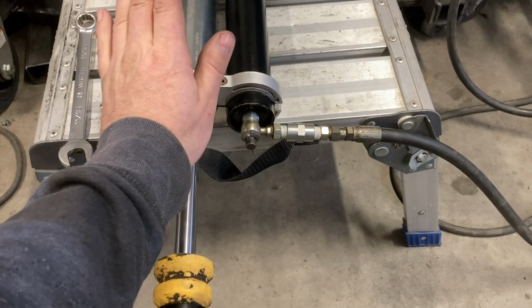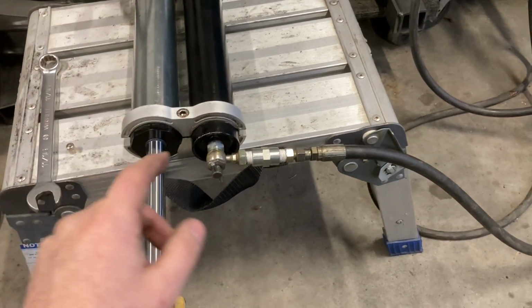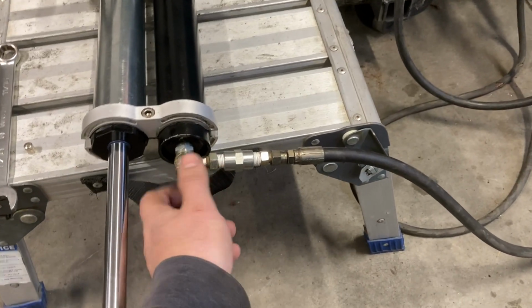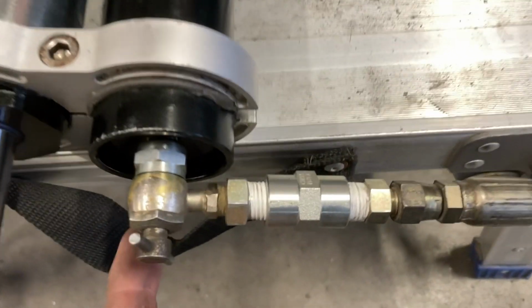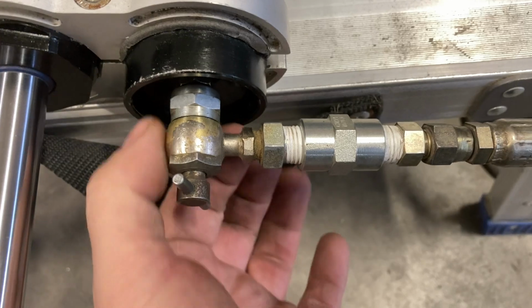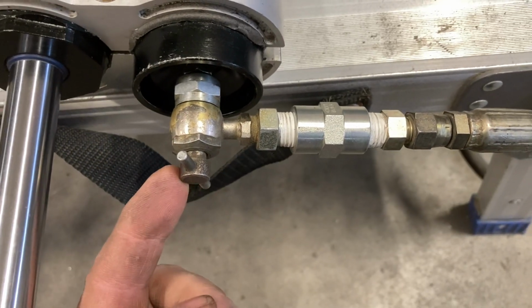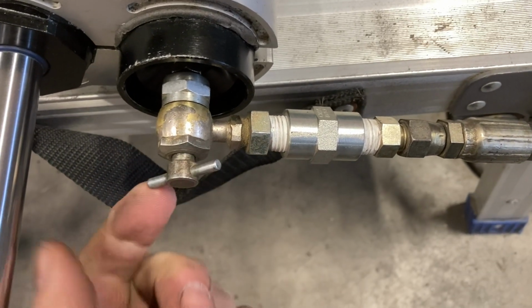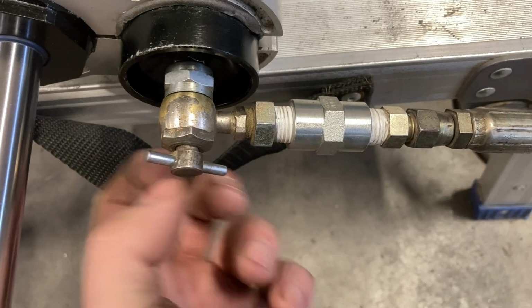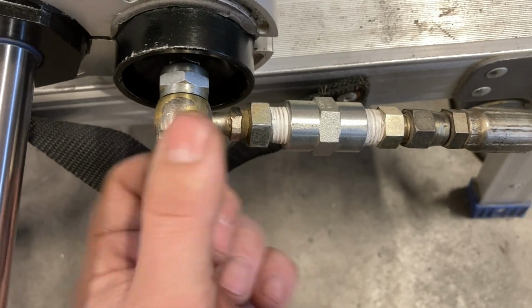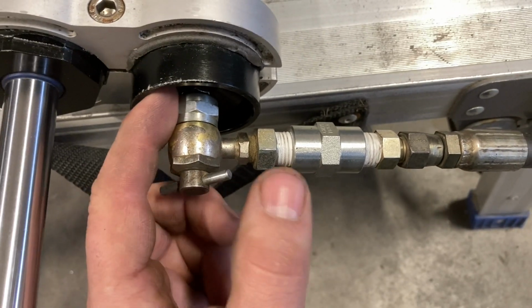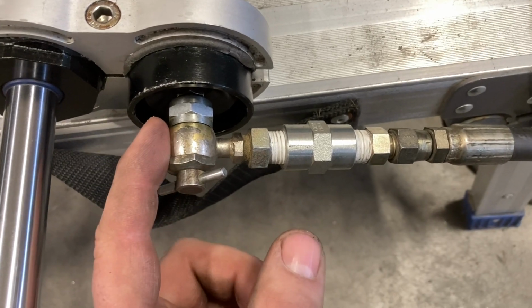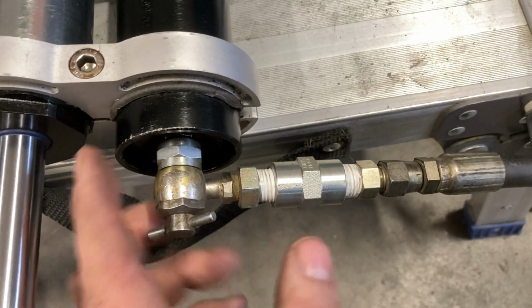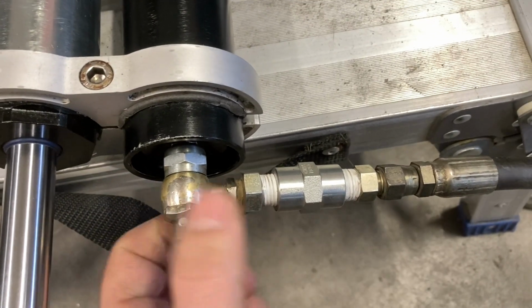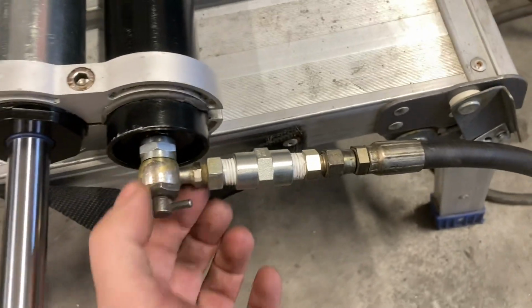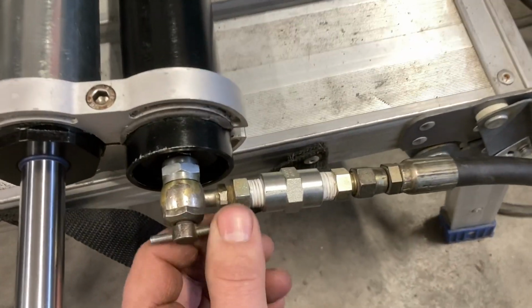Push the shaft all the way in, then hook this up - this is the nitrogen. These little fittings screw onto the Schrader valve, and this turns in and pushes the little pin in the center to open the valve. They call this a no-loss chuck. Once it's filled, you back this off to close the valve, and when you take it all loose, you don't lose any pressure.